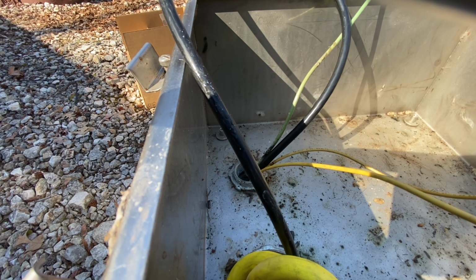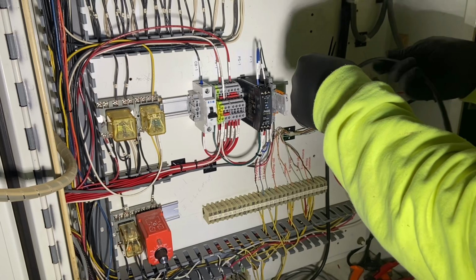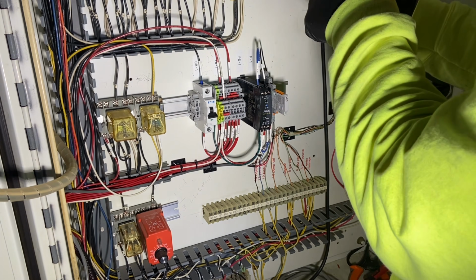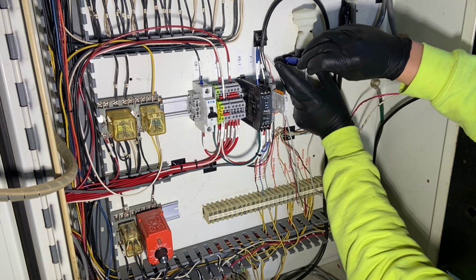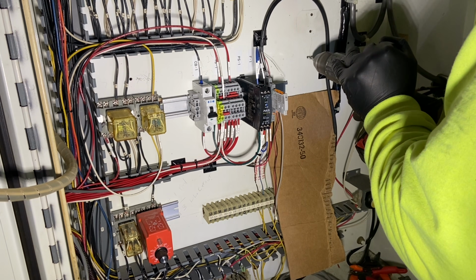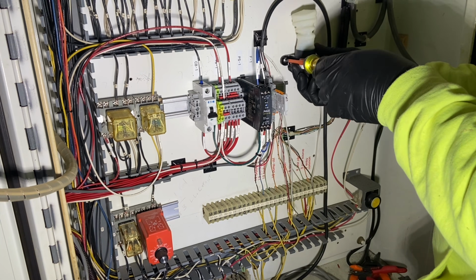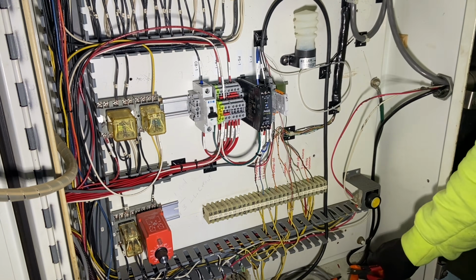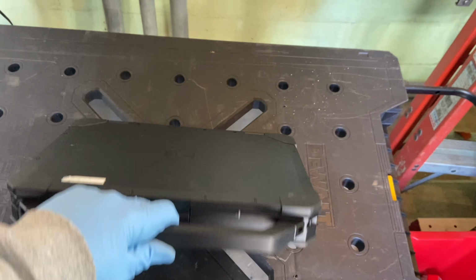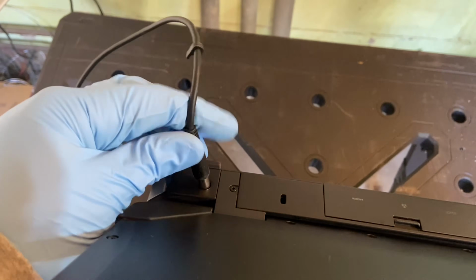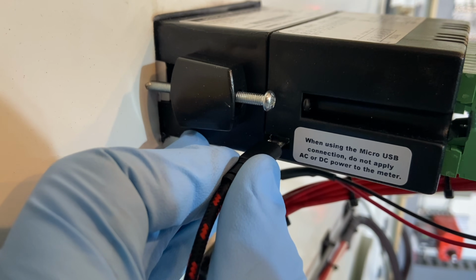Now that the electrical portion is pretty well wired up, we can pull our transducer cable in, and it's going to go up to our surge suppressor, which is that little module on the right. That is a milliamp surge suppressor. And I'll install my moisture prevention for the transducer vent tube. That vent tube just lets the transducer know what atmospheric pressure is so that it can automatically adjust, and we don't want water getting down in there.